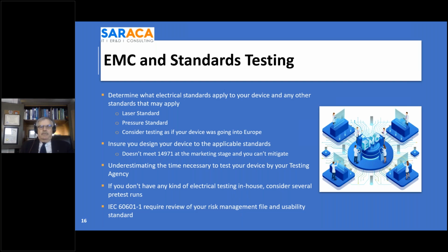I also highly recommend, if you haven't done any testing on your device, and for example, just taken the device specifications for a power supply from China, and you put it in your device and expect it to meet your noise level or emissions level, I can guarantee you that probably won't happen, because they give you an analysis that's at the very top of the spec, and your device will fail. So you need to do some preliminary testing. I recommend you do pre-testing at 2 or 3 levels. And then when you consider your device testing to be complete, you've gone through pre-testing, and everything looks copacetic, then you consider your final testing. It will cut down on the amount of testing you're doing.